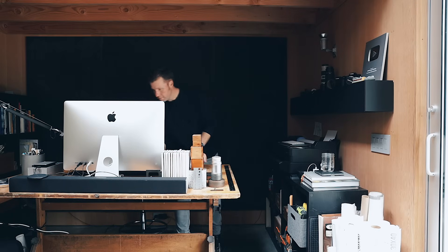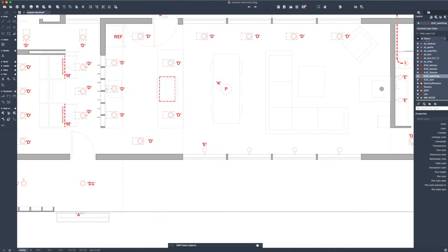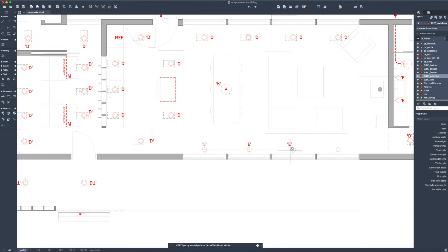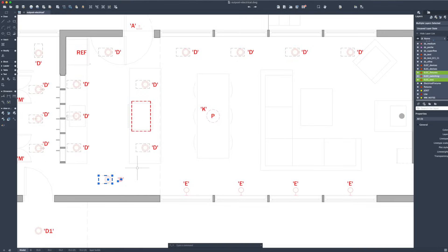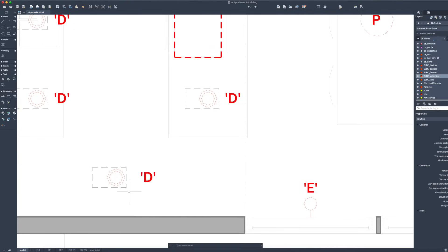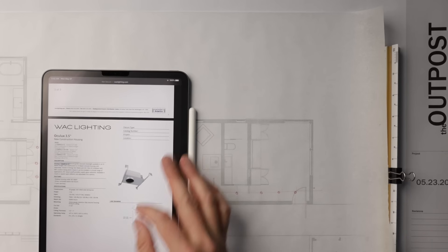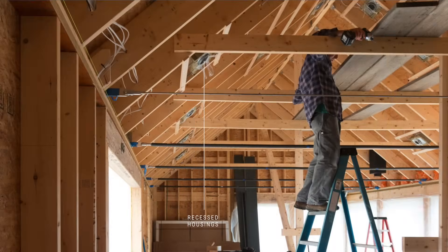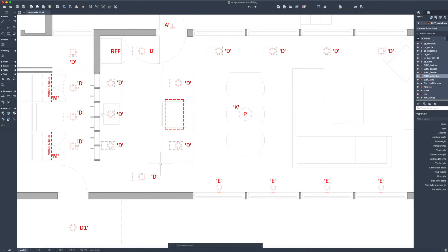We have all the fixtures sketched out — a couple of options — and we're going to get that into the digital environment and start working on the switching. Here we are in CAD. I've completed the fixture layout based on the sketches we came up with. Each one of these fixture types has a letter designation and a symbol, each called out in our electrical plan legend. For recessed lights, the fixture also has a housing I put on a layer that doesn't actually print. But I need to know where the housing is and its orientation because it's going to interface with my ceiling framing. I'll want to indicate hidden components so I know they can align with my framing layout or different structural elements in the plan.